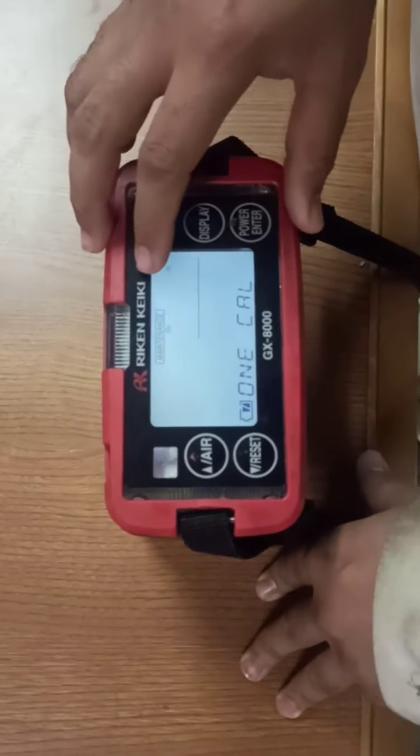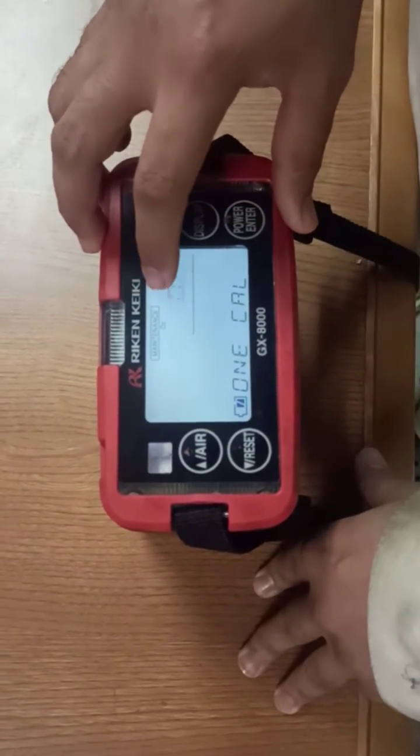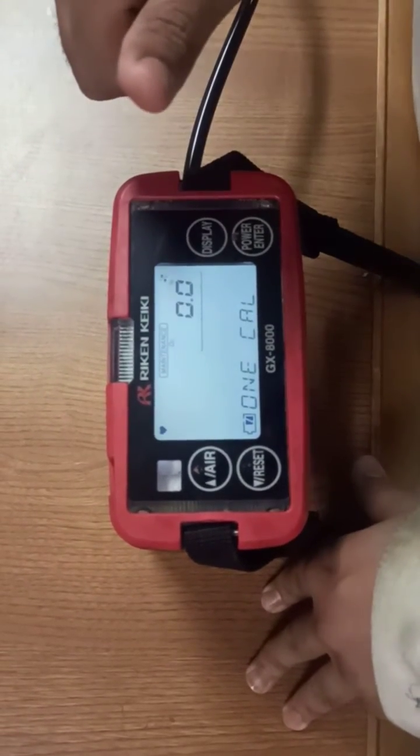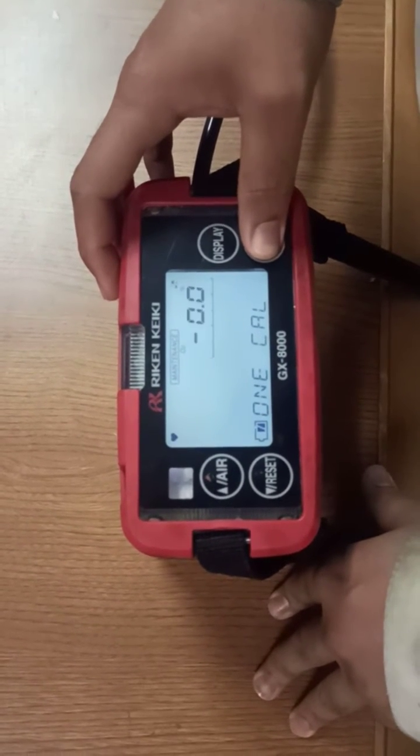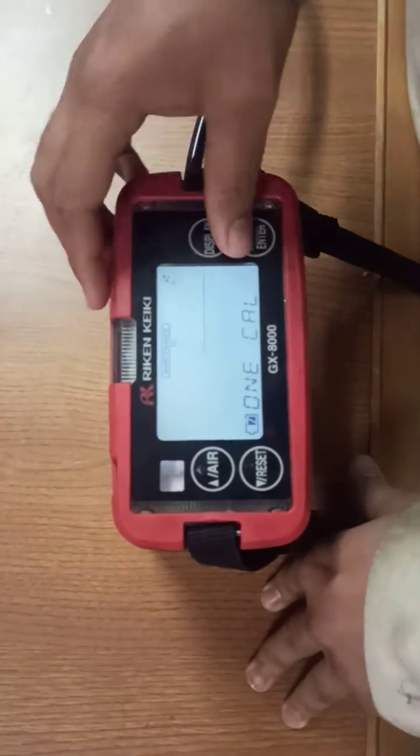As we can see, it is showing 0.0 percentage of O2, so the O2 sensor is okay and we have passed one calibration of the O2 sensor.